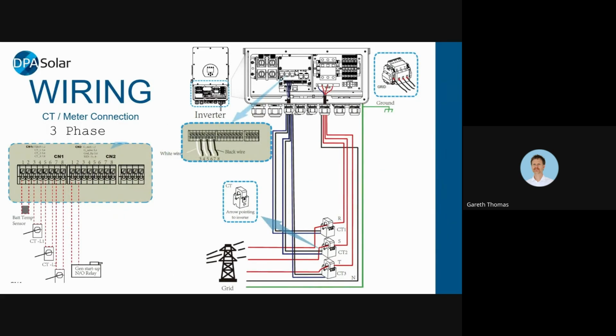And the three-phase equivalent of all of this, three-phase inverters can come with 3 CTs, and they have their assignments on these push-in connectors, channels 3 and 4, 5 and 6, and 7 and 8. That's for L1, L2, and L3.